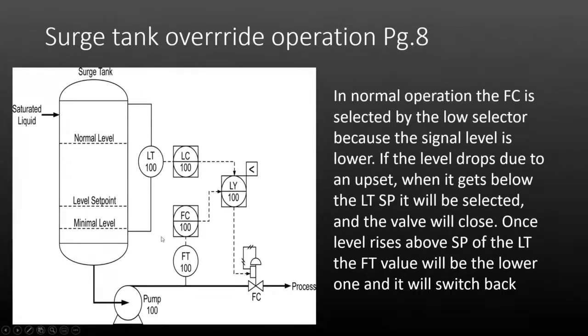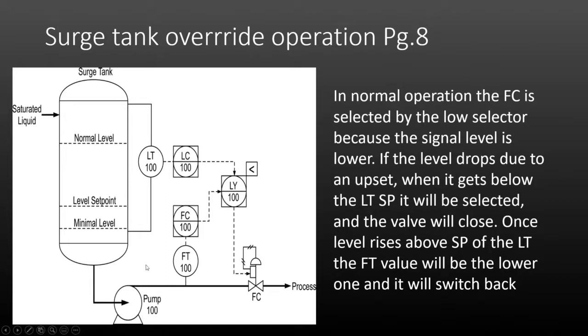In normal operation, the flow controller is selected by the low selector because its signal is generally lower most of the time. If the level drops below its set point due to an upset in the feed rate — say the flow signal is at 50% and the level drops to 25% — it's going to switch control over to the level controller until the level comes back up. Once the level rises to say 70%, it'll switch back to the flow controller.